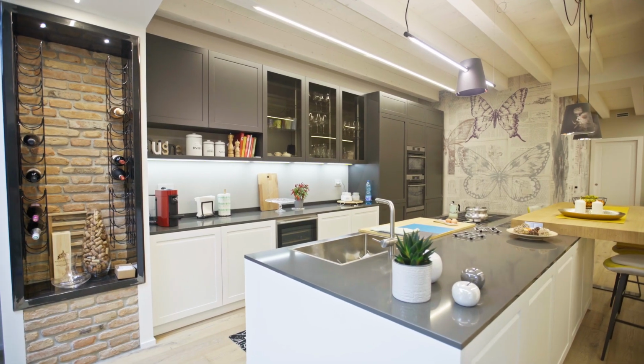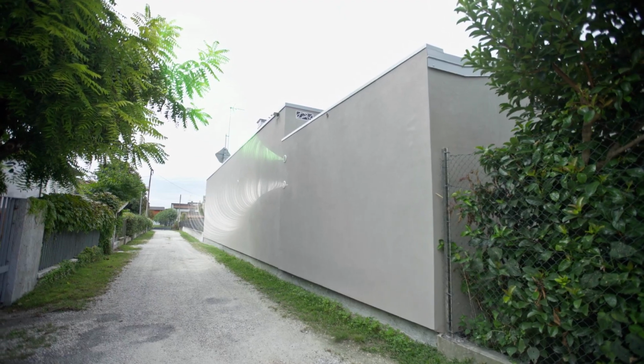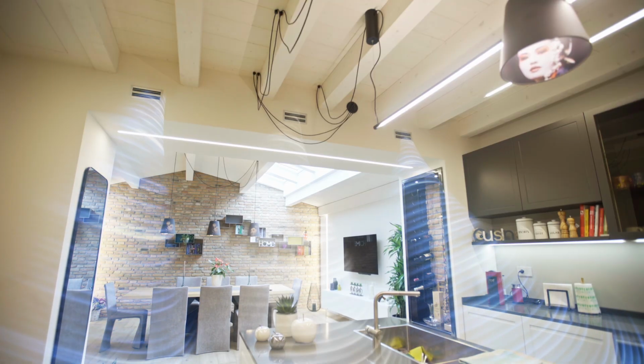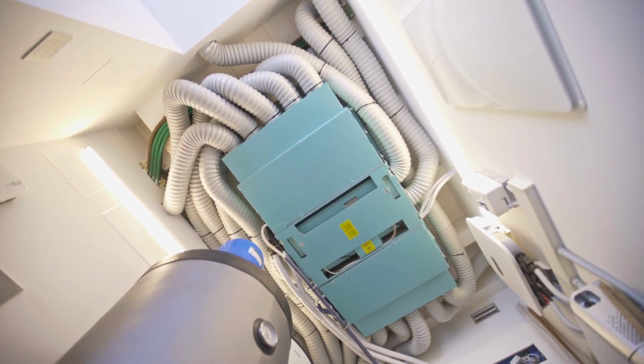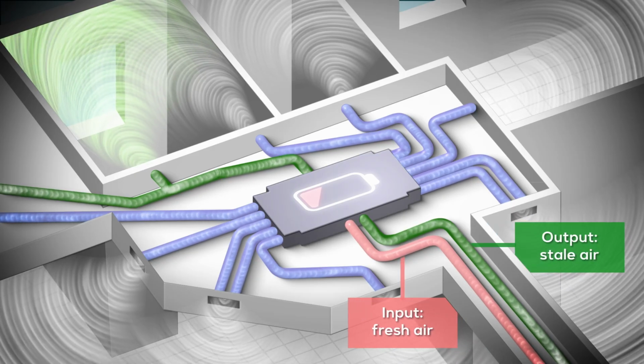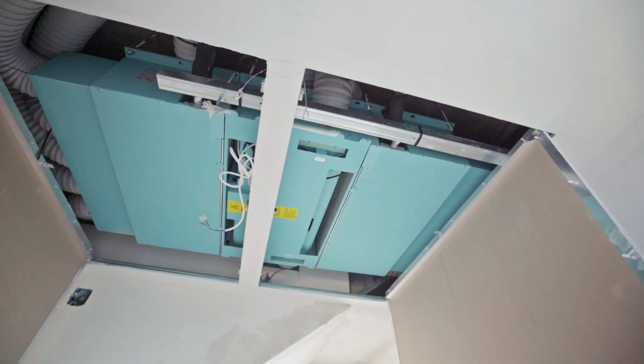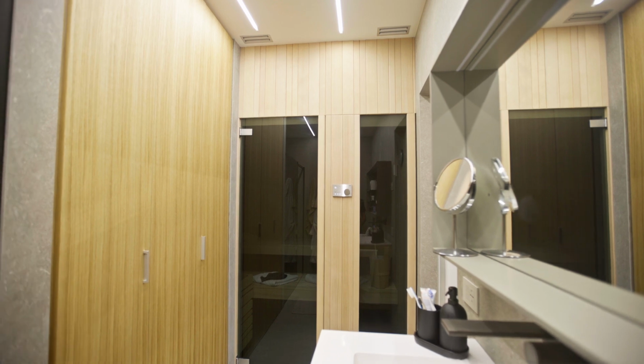The air exchange is automatic and constant and is managed directly by the unit, which draws in and filters air from outside at the same time, injecting it into the home. In this process, the air passes through the recovery unit and takes on the heat or cold recovered from the expelled stale air, depending on whether it is in heating or air conditioning mode, and reintroduces it into the domestic environment. OCTOPUS works constantly, day and night, to autonomously manage the air exchange, introducing fresh air into all rooms, thus helping to prevent mold and eliminating excess humidity thanks to the constant exchange of air.